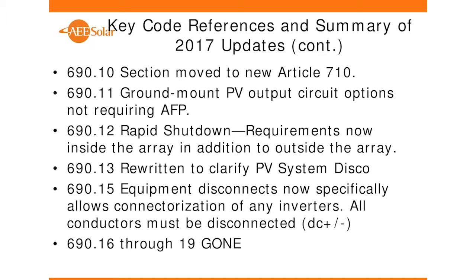And then, as I mentioned, on the disconnecting means side, what we'll get in here, it actually requires disconnecting both the positive and the negative in 690.15. 690.10, which is standalone systems, got moved to a new Article 710, so all that text was just simply moved over with a reference.